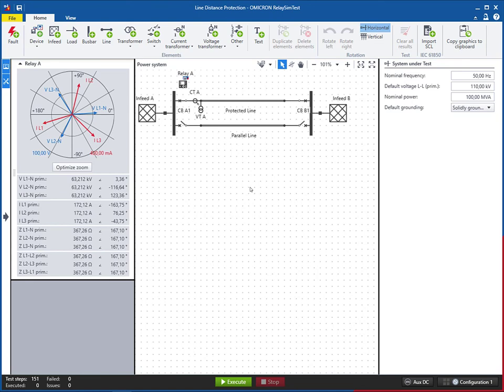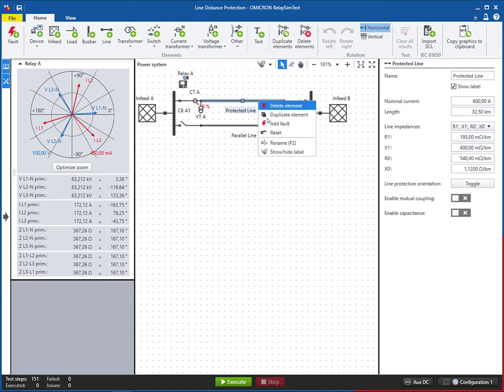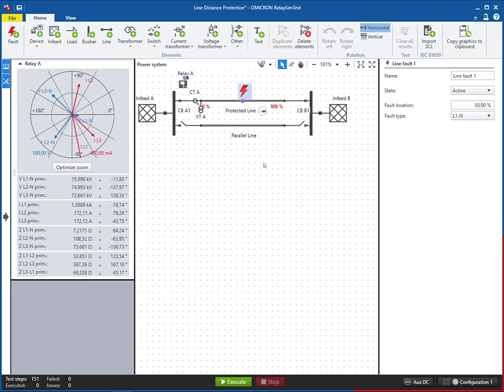This is accomplished by reproducing a part of the power transmission system in the software. In this way, RelaySimTest can reveal settings, logic, and design errors in the scheme. This is because system-based tests are independent from relay type, manufacturer, and detailed parameters.